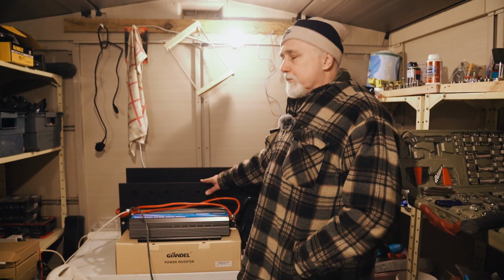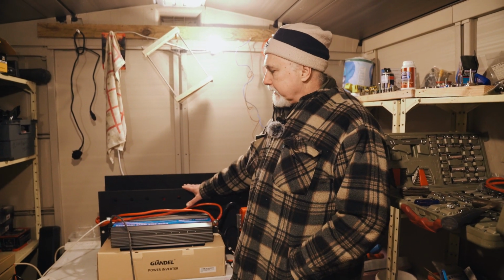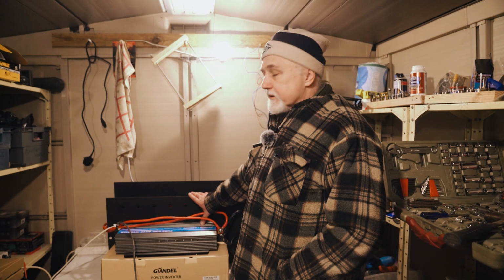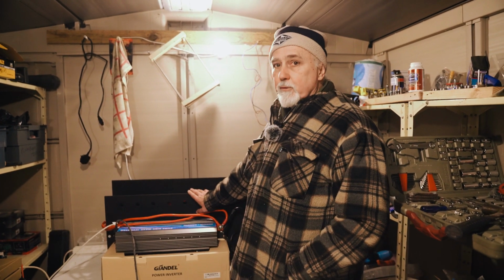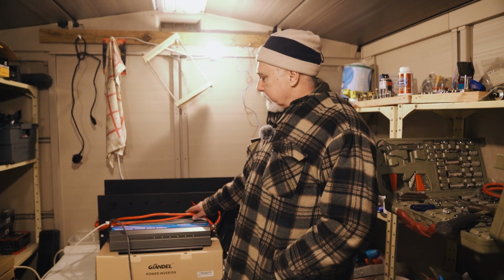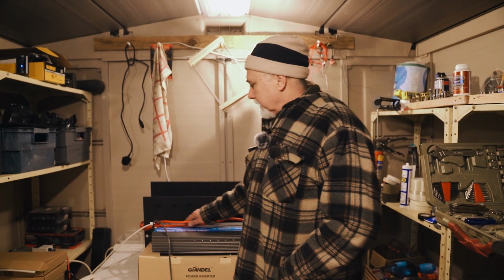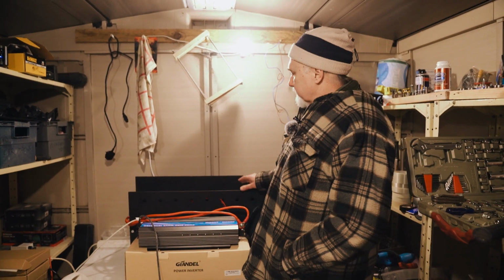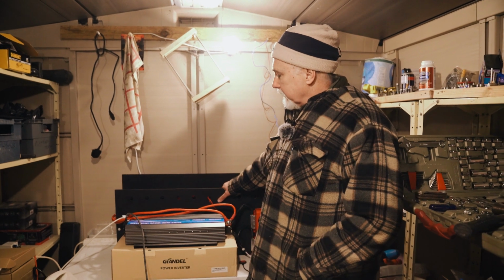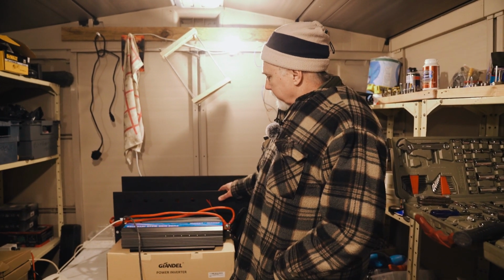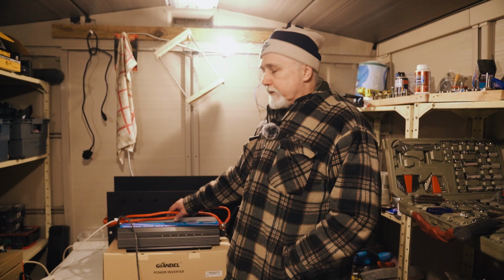We've run this down to 50% of its capacity. Bear in mind it's a 560 amp hour battery, so that's a load of power we've drawn off. We just kept coming back and checking these cables. We haven't bothered with a FLIR camera at this stage because we know nothing is going on, and probably the warmest cables are these, which are 25mm.